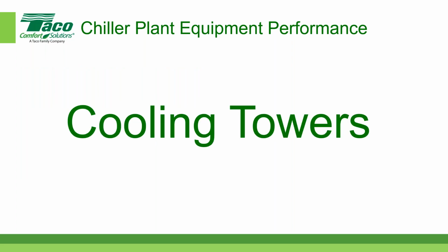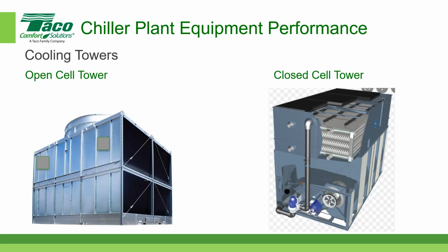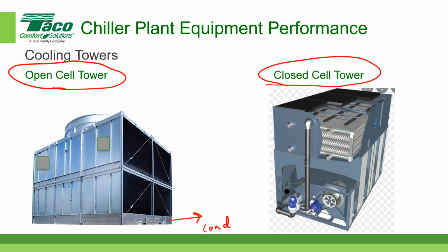Cooling towers. I'm not going to spend a lot of time on cooling towers. There are two major categories of cooling towers. The one on the left is the open cell cooling tower, and that's when the water in the cooling tower is the same exact water that's being sent to the condenser. In a closed cell cooling tower, it has a heat exchanger inside, and the water that goes to the condenser comes from the heat exchanger.